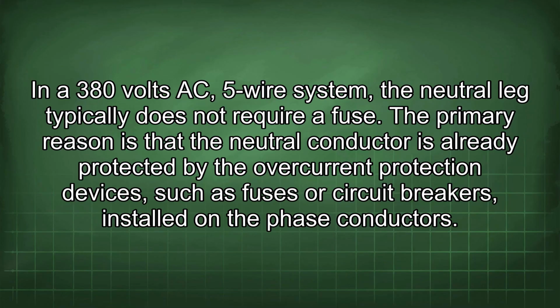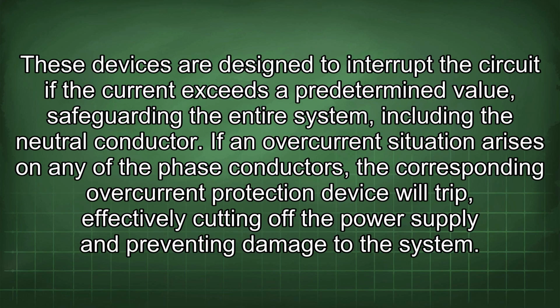In a 380 volts AC 5-wire system, the neutral leg typically does not require a fuse. The primary reason is that the neutral conductor is already protected by the overcurrent protection devices, such as fuses or circuit breakers, installed on the phase conductors. These devices are designed to interrupt the circuit if the current exceeds a predetermined value, safeguarding the entire system, including the neutral conductor. If an overcurrent situation arises on any of the phase conductors, the corresponding overcurrent protection device will trip, effectively cutting off the power supply and preventing damage to the system.